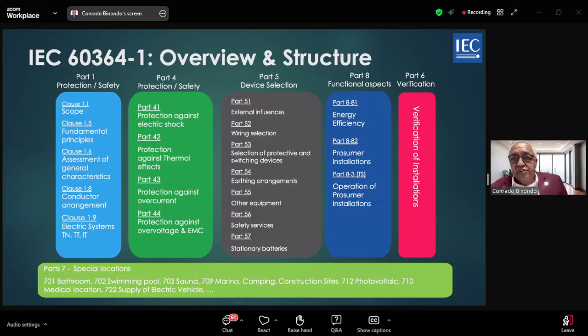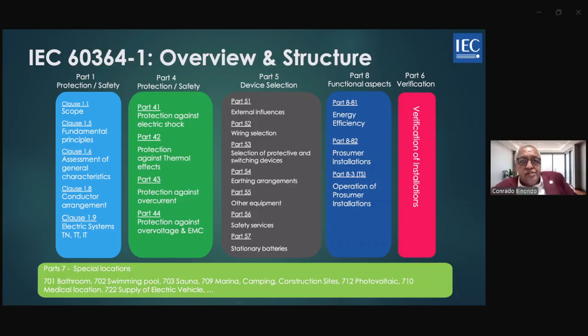So those are verifications. Now there is part 7, if you could see here. These are for special locations, because the requirements of part 5 and part 4 are general requirements, but sometimes specific requirements are required. For example, in a bathroom, there are specific requirements on how to install protective devices like residual current devices. There are special ways on how to do it. In 702 swimming pool, it is treated differently. There are special requirements, so we cannot cover this generally in protection against electric shock - how to install in a swimming pool is different. There are specific requirements and so on and so forth. Then even in PV, there are special ways to construct a safe PV installation.